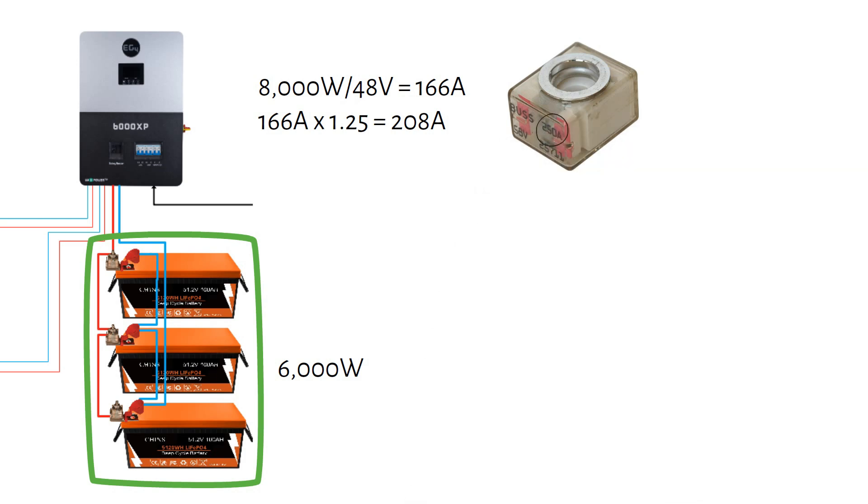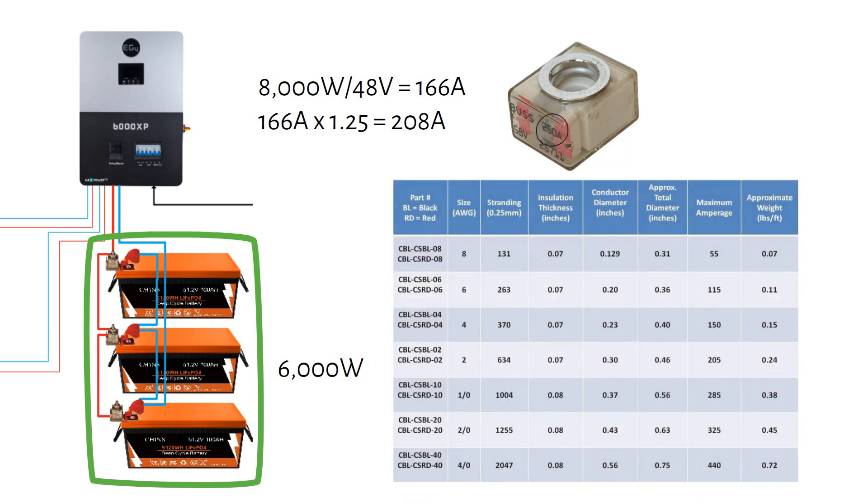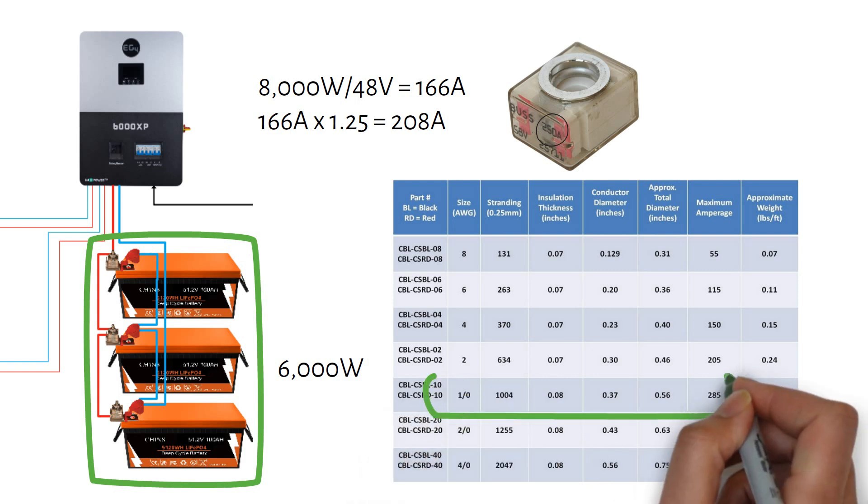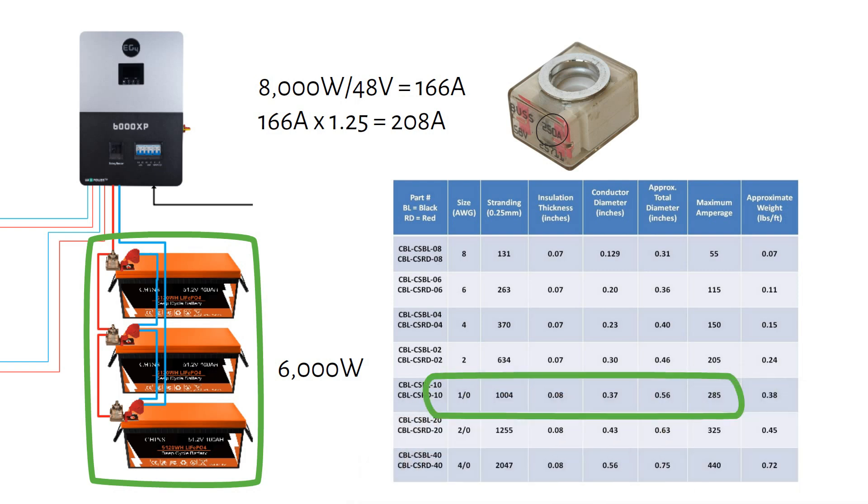Next, we have to find the cable that can carry at least the fuse rating, which is 250A. A 1/0 or 55mm square welding cable is rated for 285A. A total of 20ft red and 20ft black will cost you $180 including lugs.